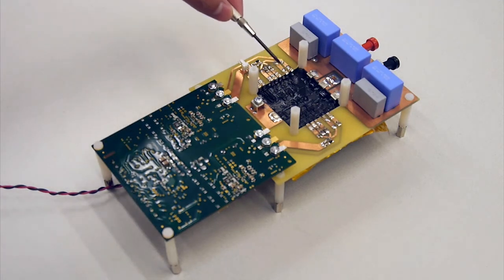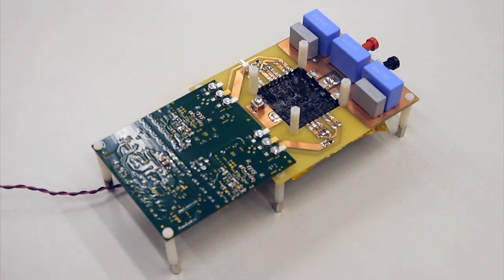On the right hand side, you can see this is a power module. For this particular module, we didn't use the silicone encapsulation. Instead, we coated the module surface using a thin layer of black color dielectric paint to increase the emissivity of the surface, so that during the test, we can measure the device temperatures using a thermal camera.